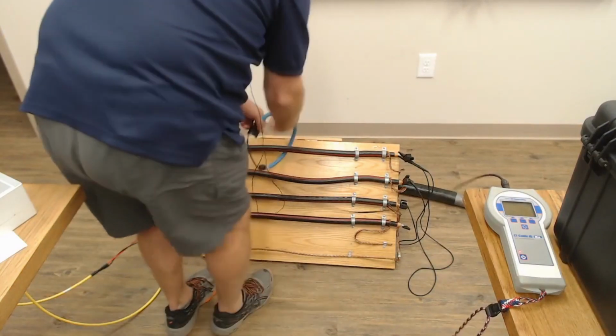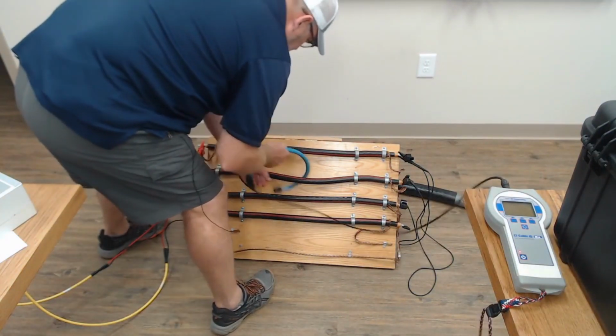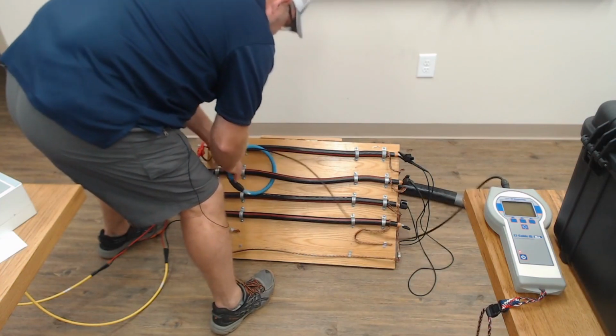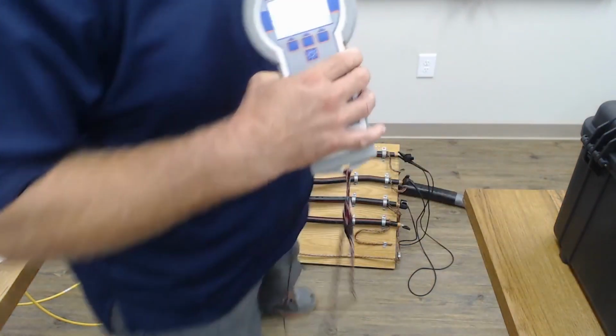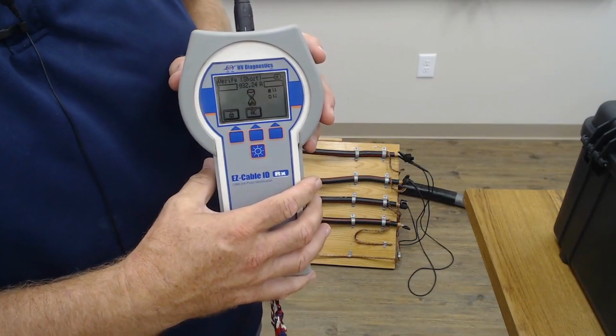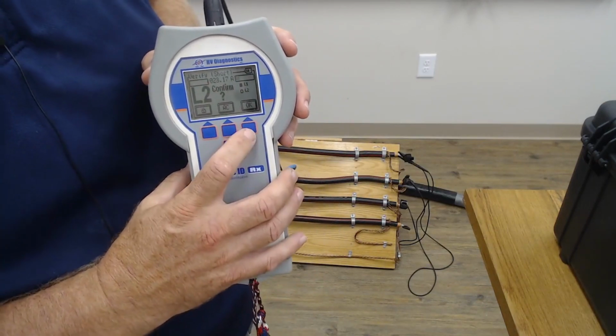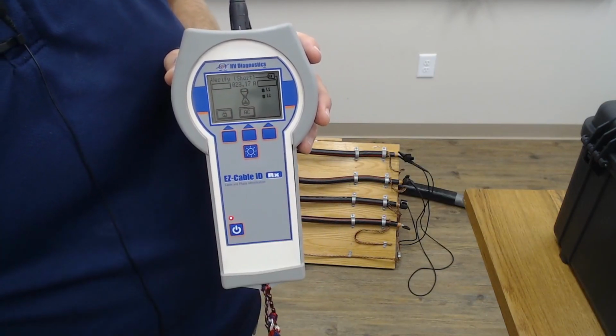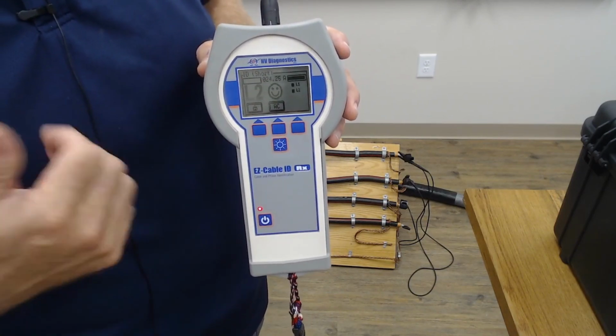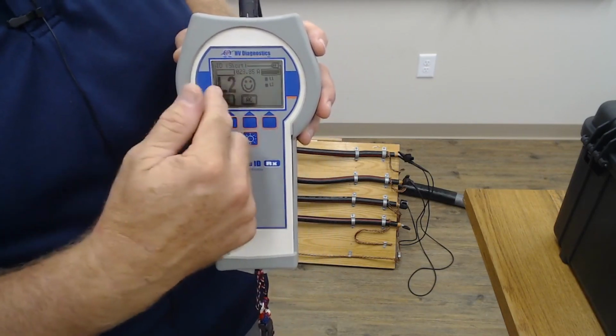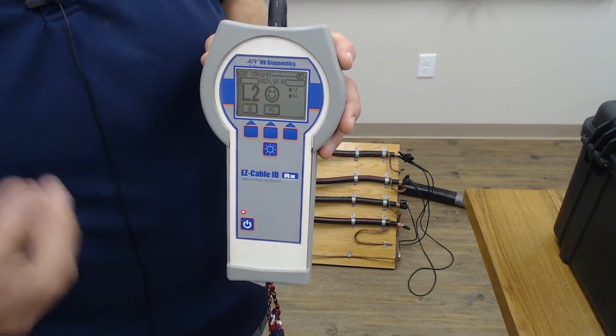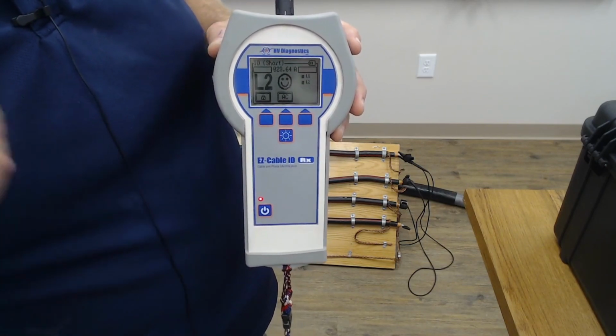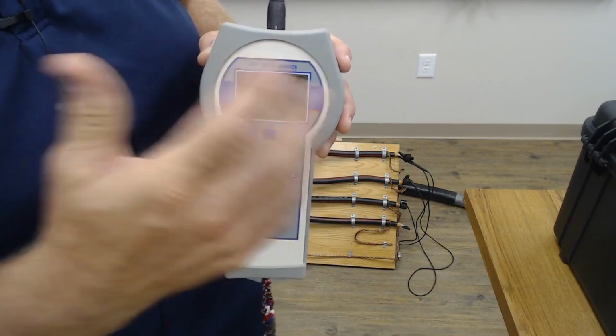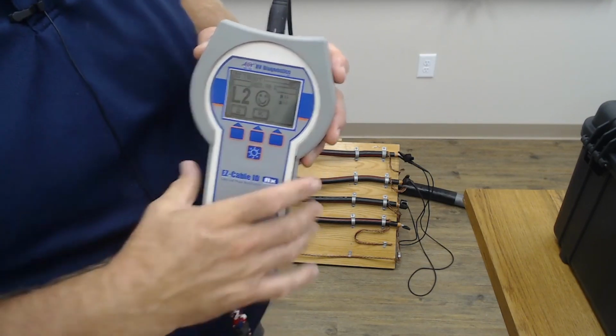Then you go to your second phase, your L2, and you do the exact same thing, and it should come up and say to us L2 question mark, and that's exactly what it says, and you say yes it is. And now it will store that information inside the unit. Now you see an L2 smiley face. That means that you've met the threshold, that exact current that it is looking for down the line is exactly correct. Well, obviously we haven't moved this yet, so it would be correct.